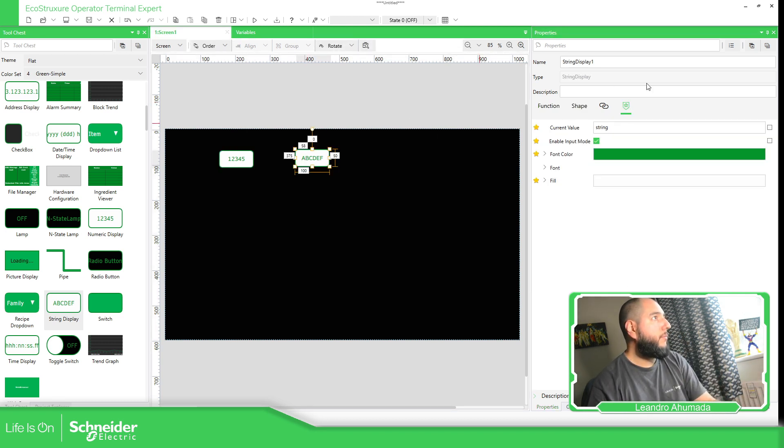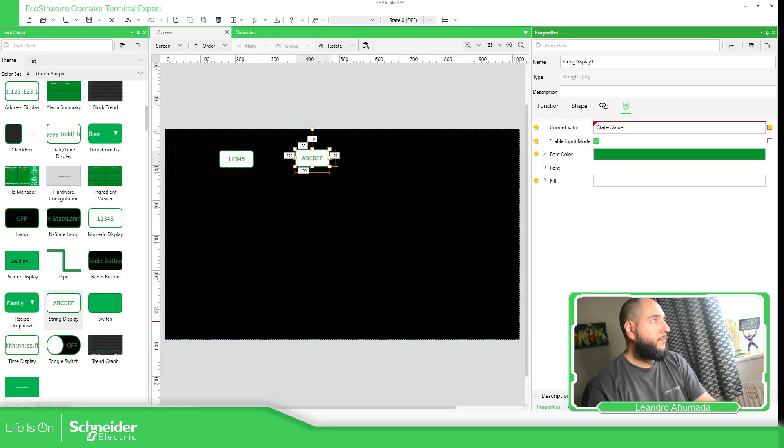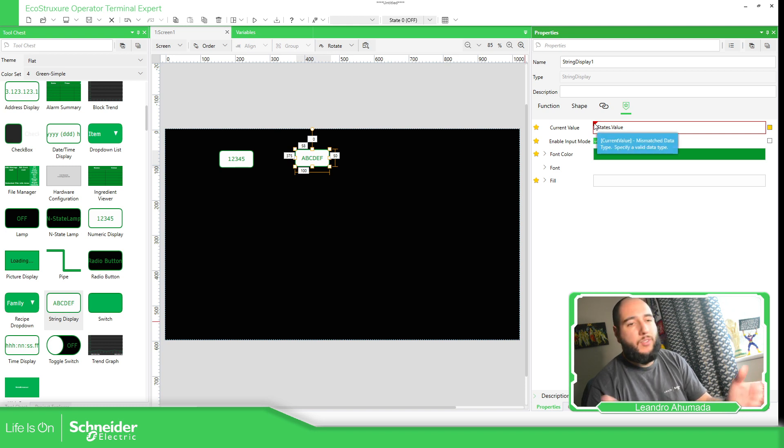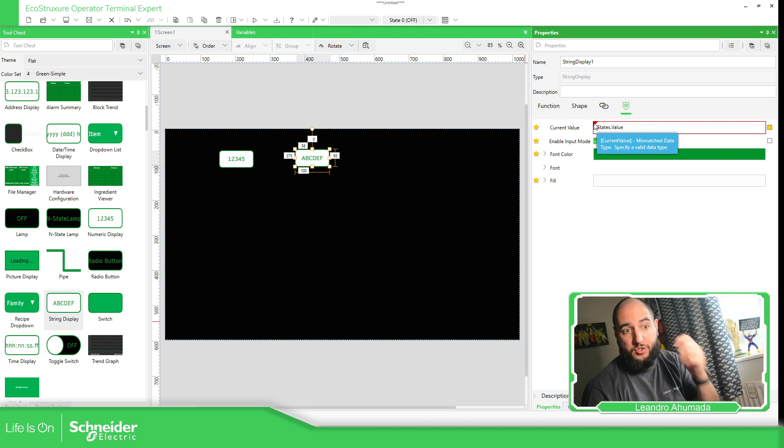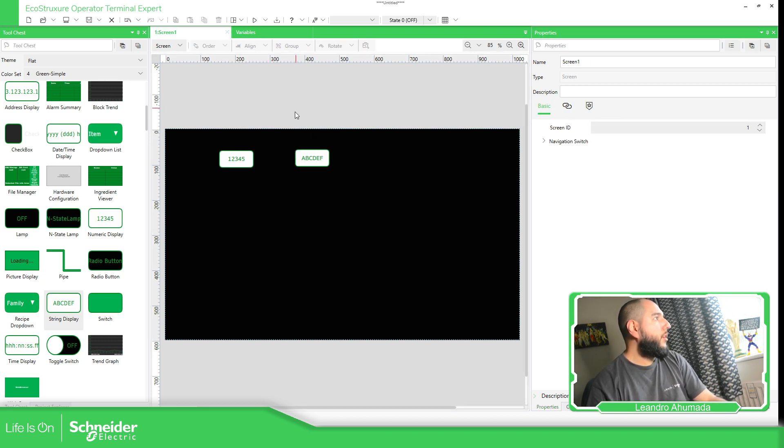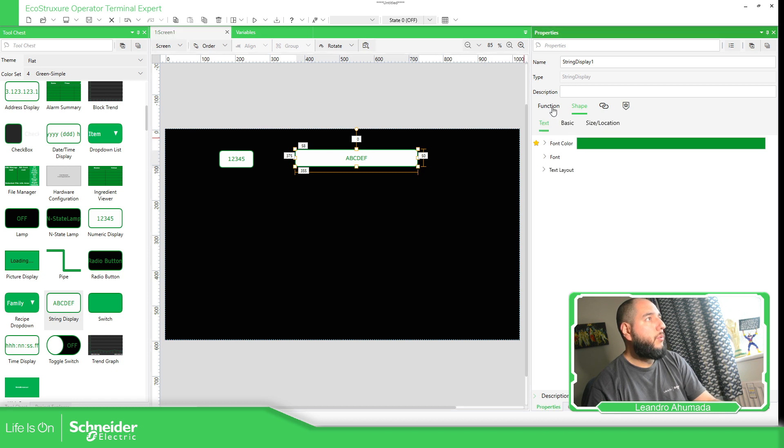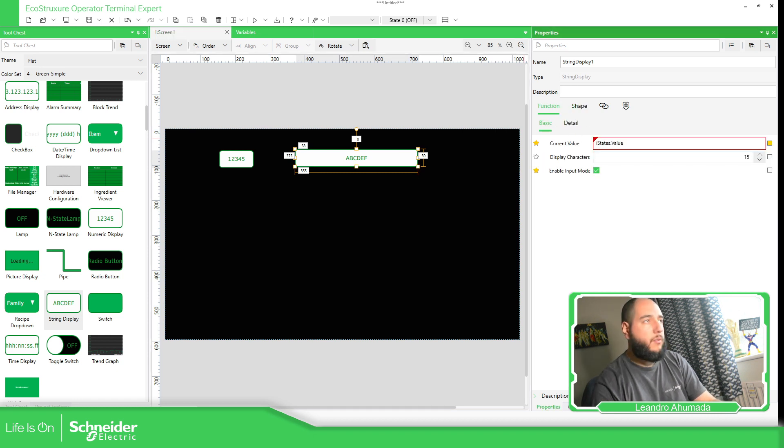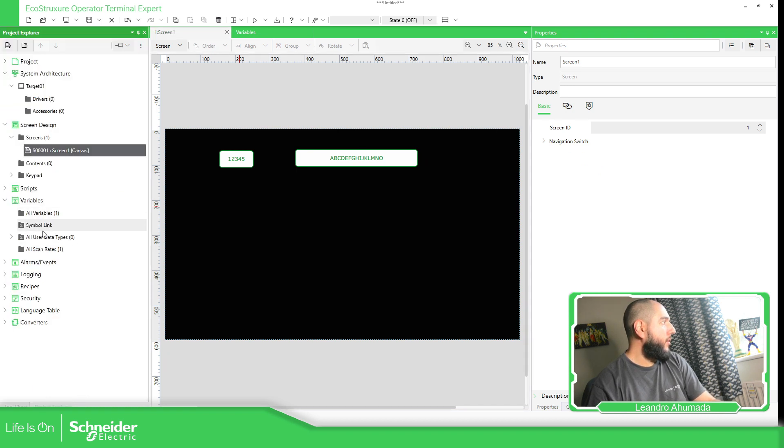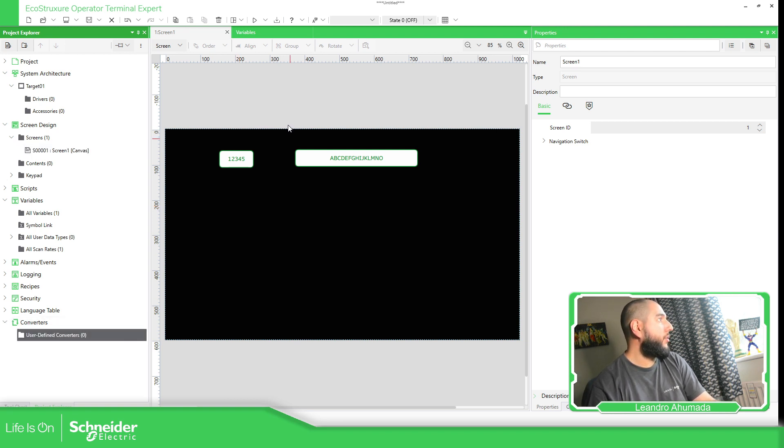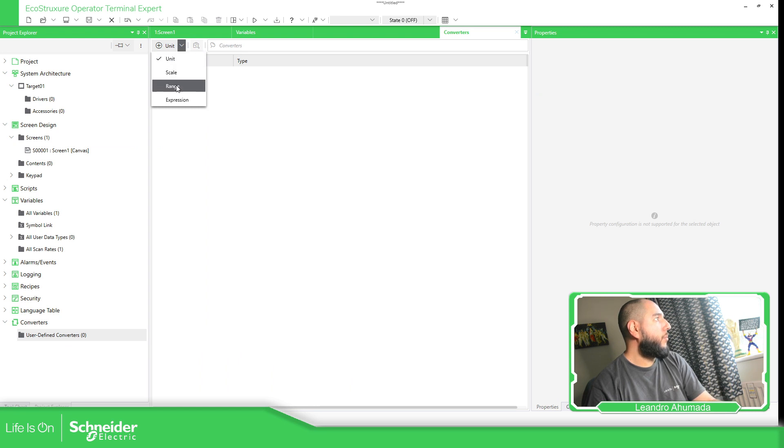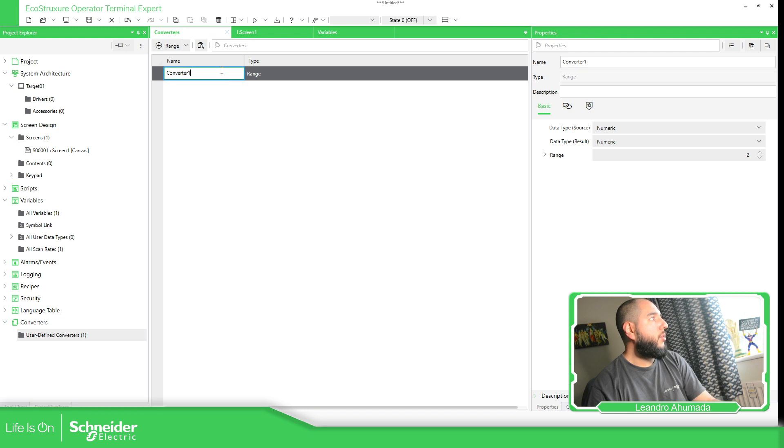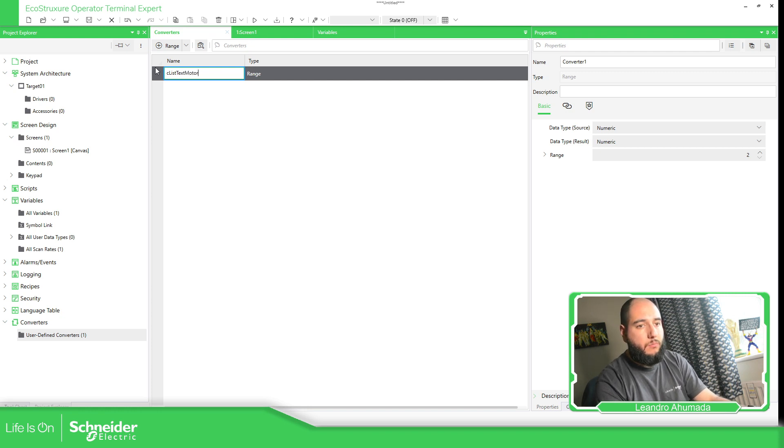Now on the string, if we try to select this variable, we got this message because there's a mismatch. We are trying to use in a text an integer value, that is not a string. So we have an issue. So in order to sort this out, in EcoStruxure Operator Terminal Expert, the key here is to use the converters. So here we need to use converter range. So list text set motor. The input for this, imagine like if you have a function block with something in the input and something that's going out. So numeric input and the result is going to be a string.